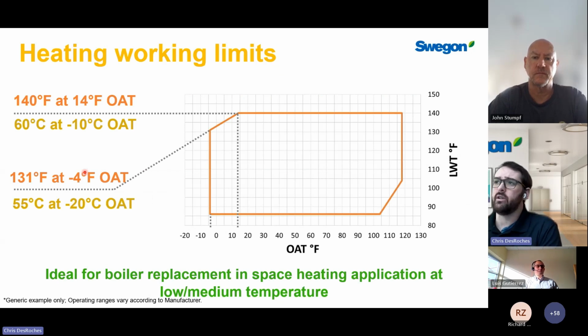So just to recap, I don't believe we had the testing finalized when we did the previous presentation in May, but the operating testing has all been finalized and confirmed. So we're using liquid injected compressors as standard on our heat pump model. This means we can generate 140 Fahrenheit water down to as cold as 14F ambient temperature. As our ambient temperature drops from 14, it's a little bit harder to extract heat from outside using the air, and we end up having a lower lift on the compressor essentially.